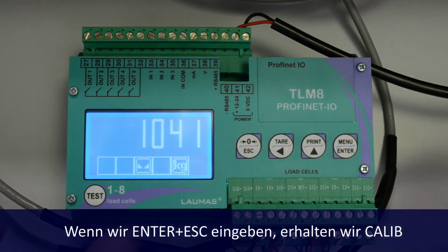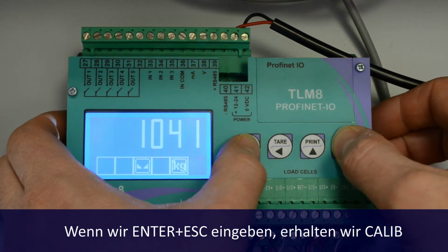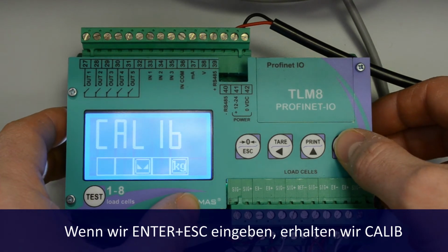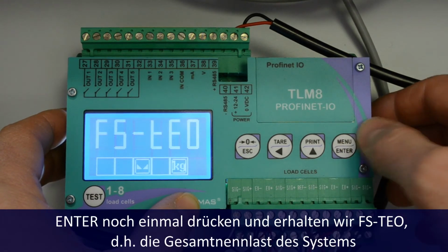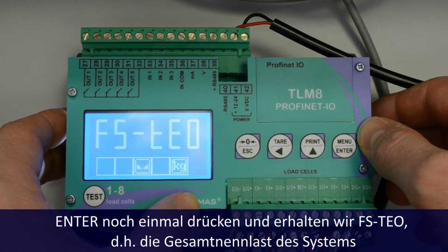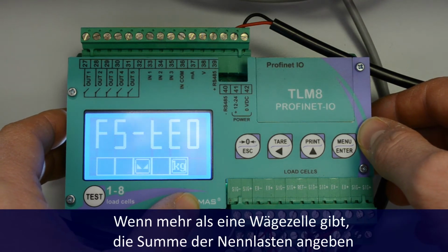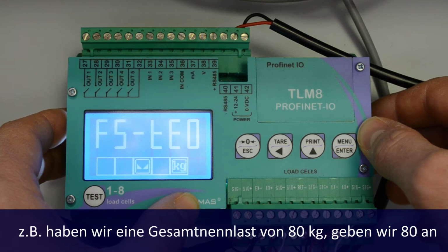Okay, entering the menu with Enter plus ESC, we get Calib. Enter, and we see FS-TEO, which is the total capacity of the system. If you have more than one load cell, you have to put here the sum of the capacities of the load cells. In this case, we have a total capacity of 80 kilograms, so I will type here 80.